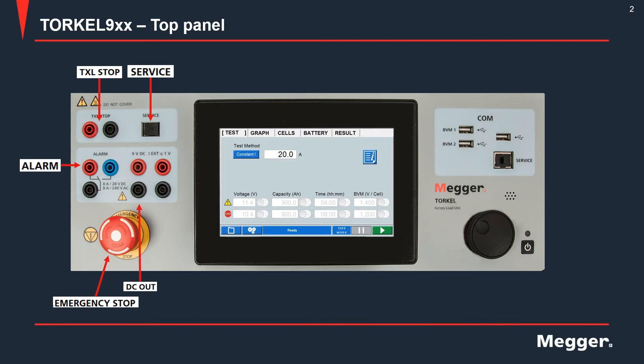There are a couple of binding posts provided to supply a DC output to the DC clamp-on that you may use if you want to measure current externally. If you are using the DC clamp-on, the feedback voltage signal from the clamp-on would come back on these binding posts. The feedback voltage signal needs to be less than one volt.